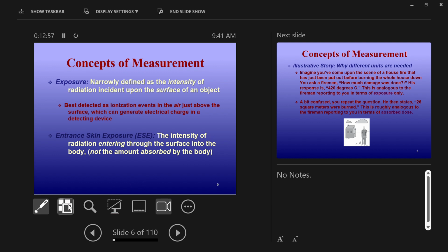Is this also how we measure the exposure deviation when we take the X-rays? In a way. When you measure exposure deviation, the detector knows how much it's expecting, right, and how much charge it actually gets, and it compares how much charge it received. So the X-rays hit the detector and it creates some electric charge. It's comparing how much charge it expects versus how much charge was actually received, and then it gives you an amount. But it's not measuring exposure though. It's measuring more like an absorbed dose kind of thing. It's a little different.